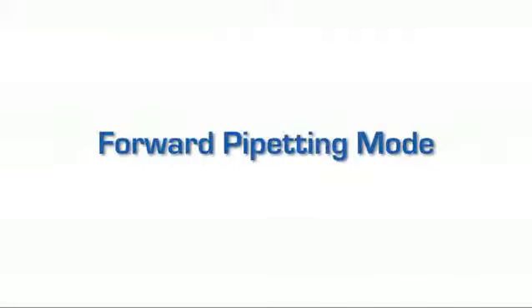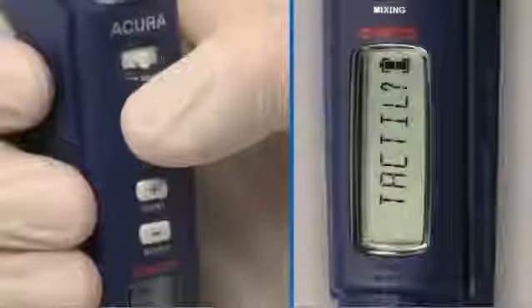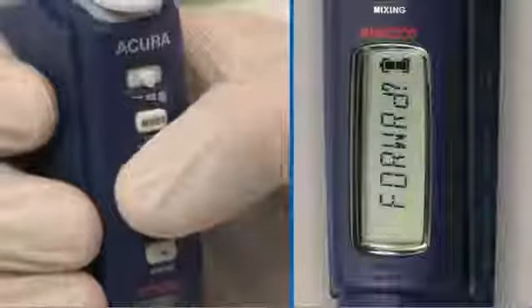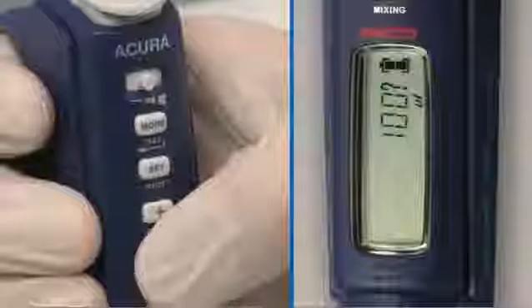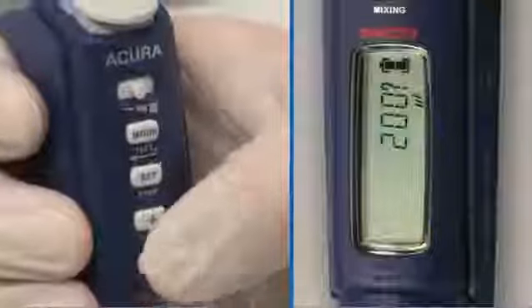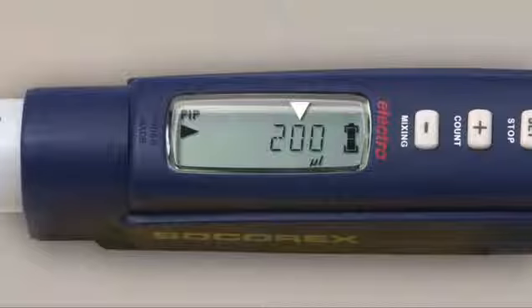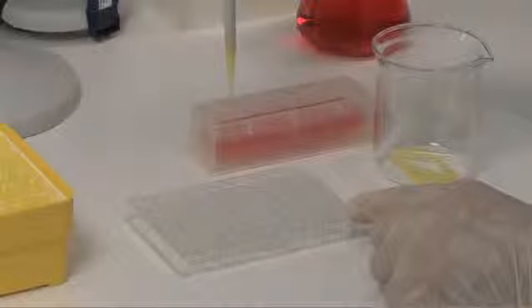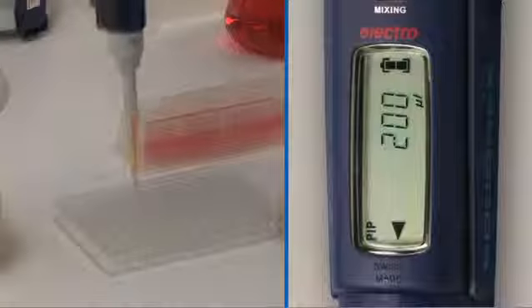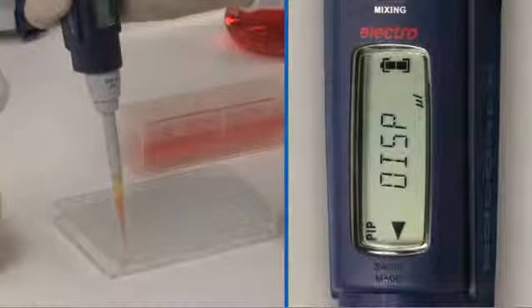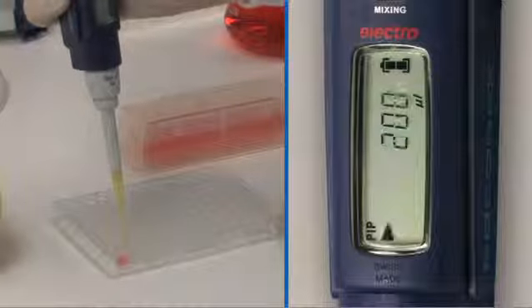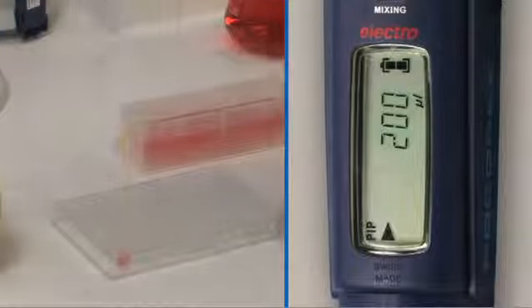Forward mode corresponds to aspiration and pipetting of a set volume. It's suitable for all applications in the lab. Press Mode until the display shows forward. Press Set to validate. Press the plus/minus keys to display the desired volume. Press Set to validate. The display shows the selected mode and volume. The instrument is ready to aspirate in forward pipetting mode. Aspirate the liquid, and the display shows that it's ready to distribute. After distribution and overshoot, the display shows it's ready to aspirate again.